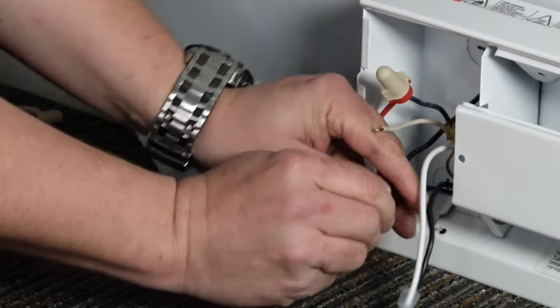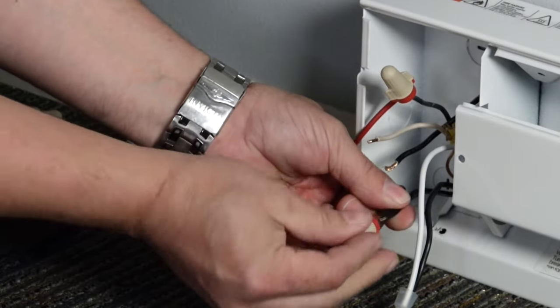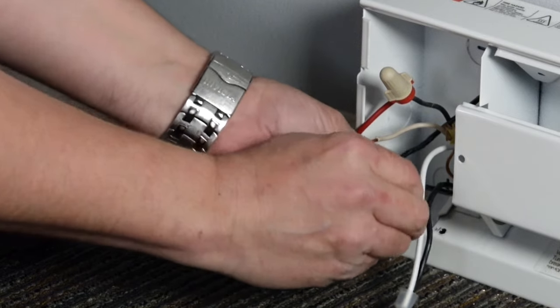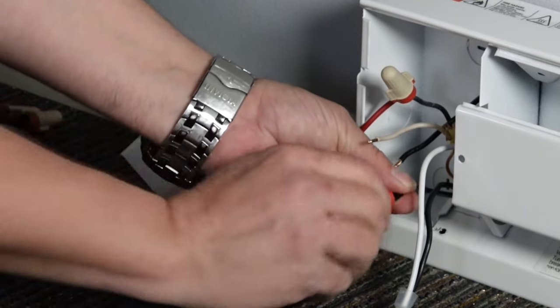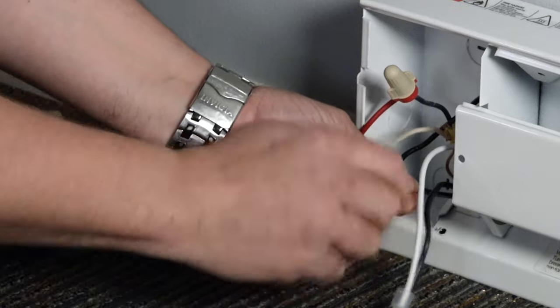Now take the black supply wire coming from the wall and connect it to the red wire on the thermostat. Then take the black thermostat wire and connect it to the black wire on the heater.